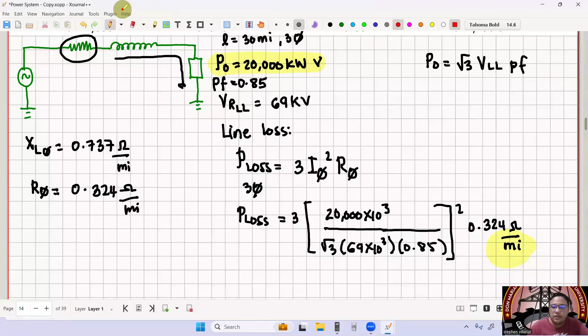So what's now your P loss? This is now 3 multiplied by 20,000 kilo over square root of 3 multiplied by 69 kilo times 0.85, the quantity squared, times 0.324 times 30. So this is now equal to... wait.